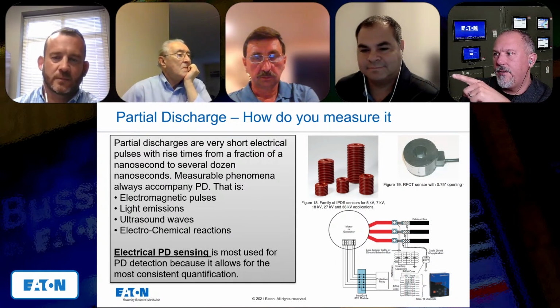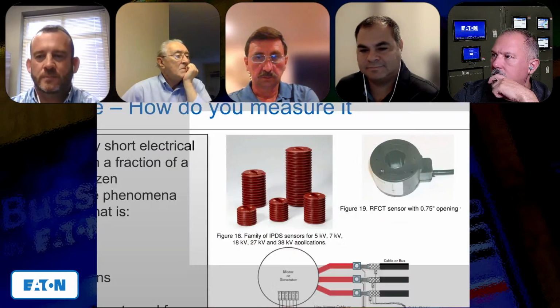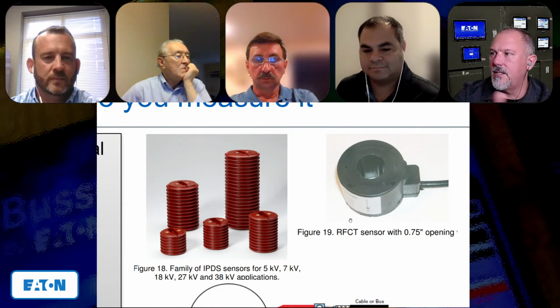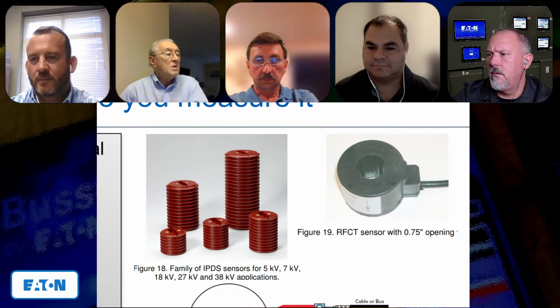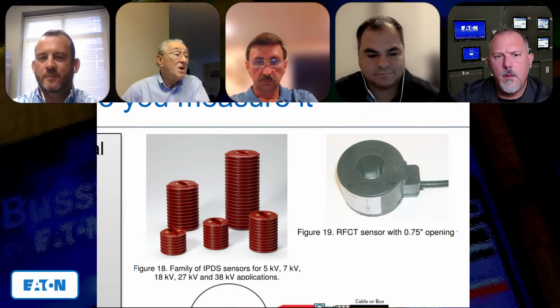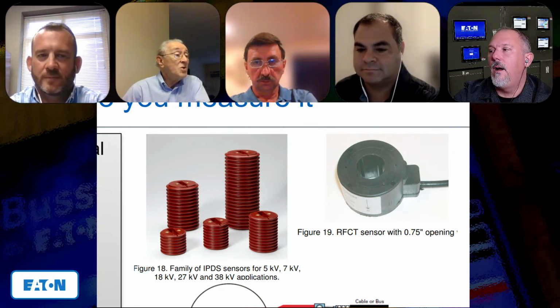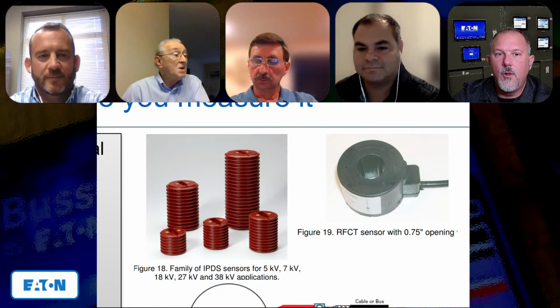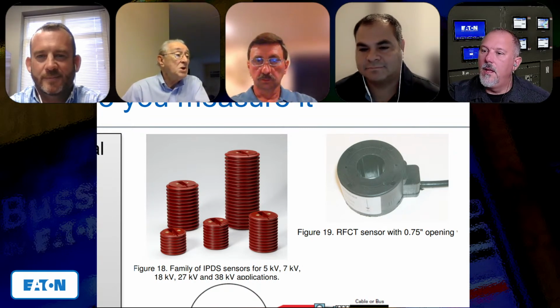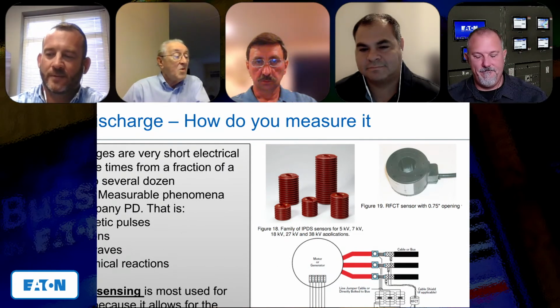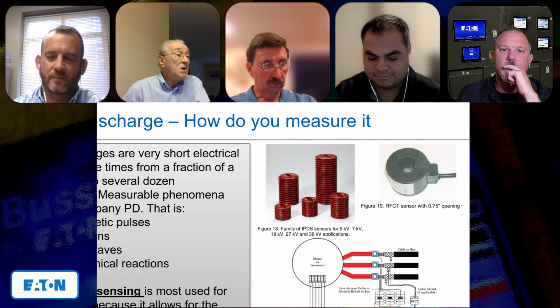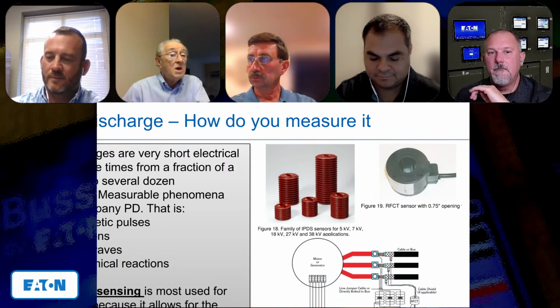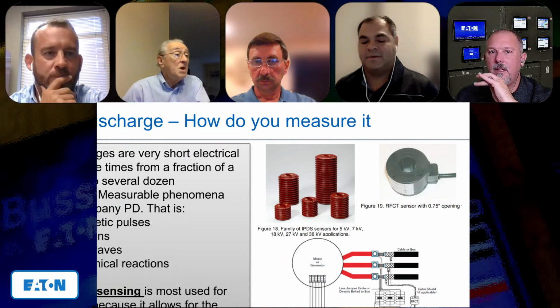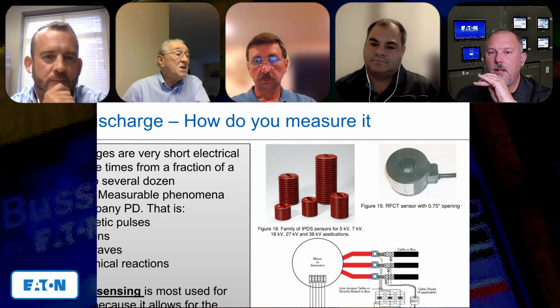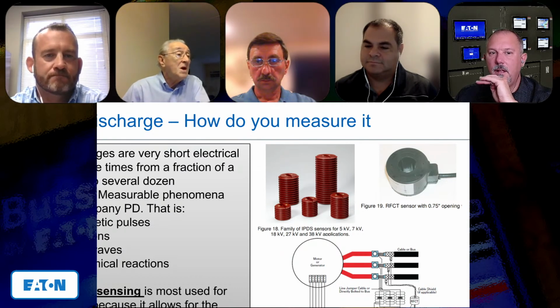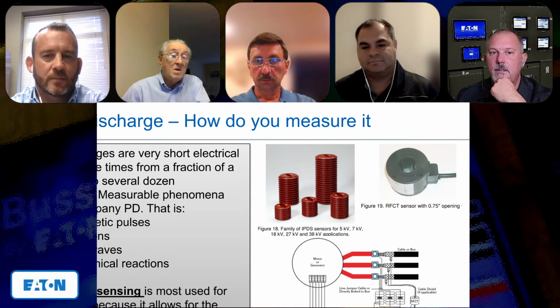So what are we looking at here? This sensor that's in the top right side. What's this guy here? Is that just a CT or is that something different? Yes, it is a current transformer, radio frequency range. This current transformer should capture the partial discharge in the frequency range from 1 to 20 megahertz. Really, partial discharge is very short pulses. The duration should be measured in nanoseconds, some nanoseconds or some dozens of nanoseconds, and they have a very wide spectrum.